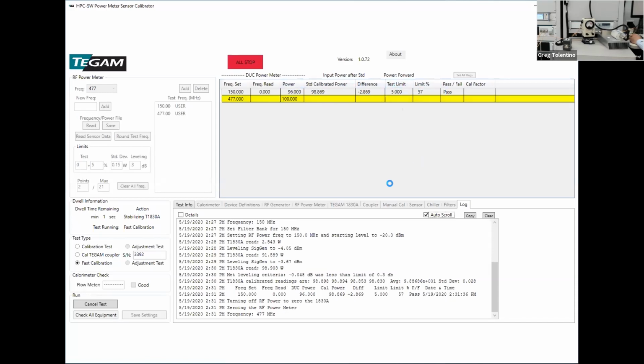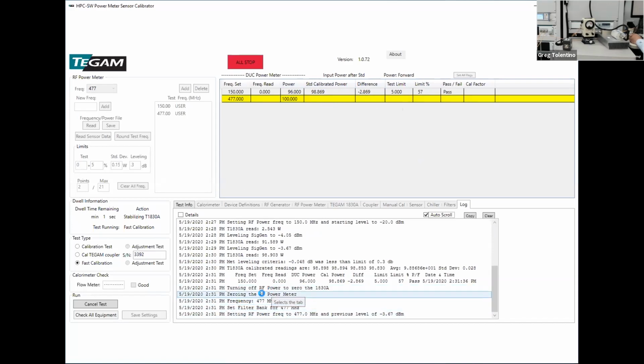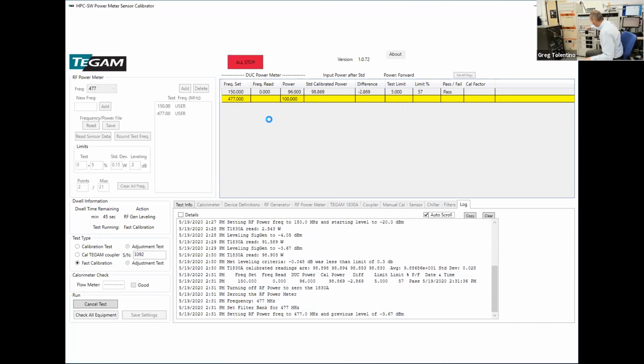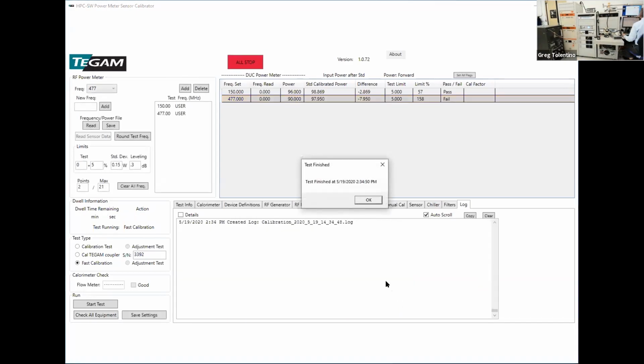And in the meantime, while I've been talking, it went ahead and zeroed the 1830, set the switches for 477 megahertz, and it also rerouted the power. So over here, the big amp is done at 225 megahertz. So we had to send commands to the signal router to bring this amplifier here into play, all automatic. All right, test finished up. We can see that we're at 158% of the test limit at 477 megahertz, so we had to fail a unit.